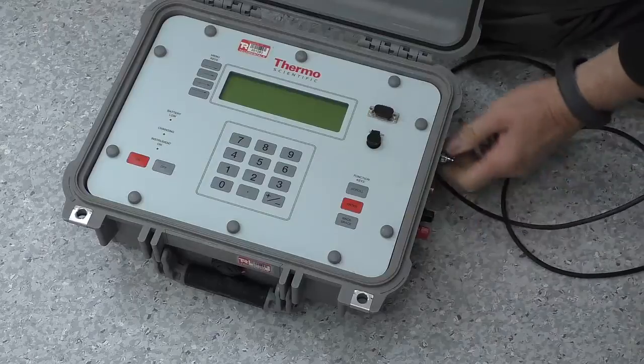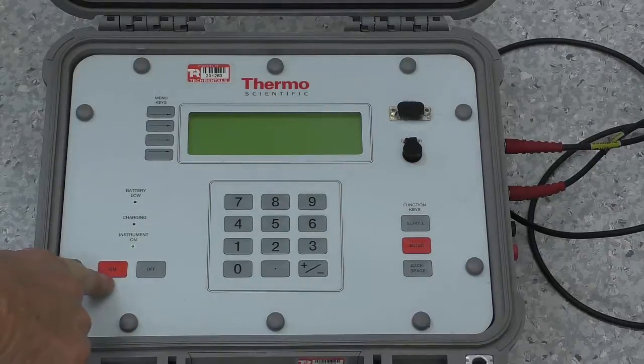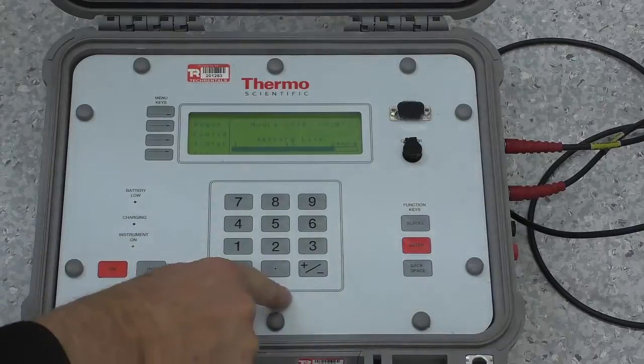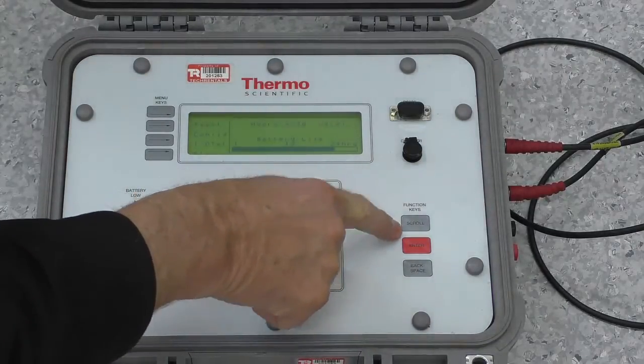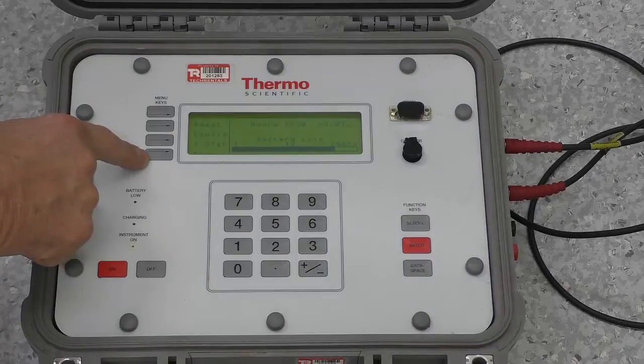I've opened the instrument up. They're simply BNC connectors, so we connect them here. Now we just simply switch the instrument on and hit the on switch. The instrument's on and it's booting. We've got a keypad here for entering numbers. Scroll jumps between fields, and there's an Enter key and a Backspace — they're the only function keys — as well as these soft keys up the top here.